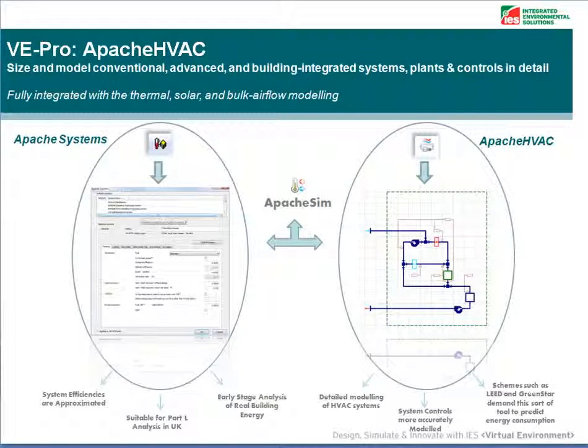Apache Systems allows you to create simple system representations in the Apache Systems dialogue, allowing the input of seasonal energy efficiencies for heating and cooling plant, as well as auxiliary energy values to represent the power consumed by pumps, fans and controls, so the system efficiencies are approximated.